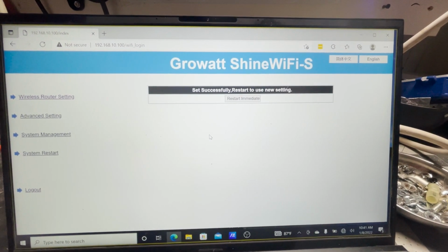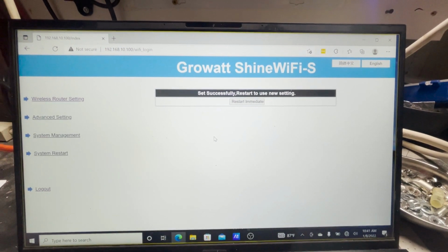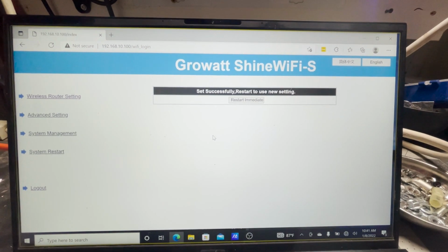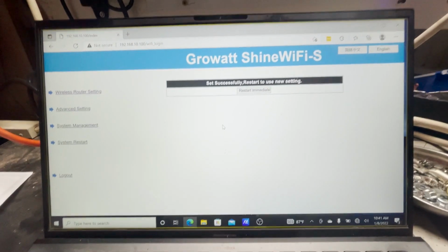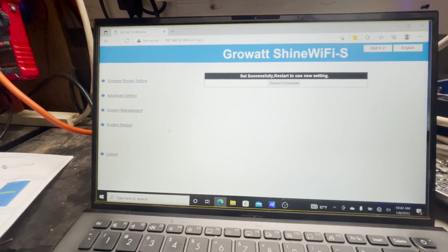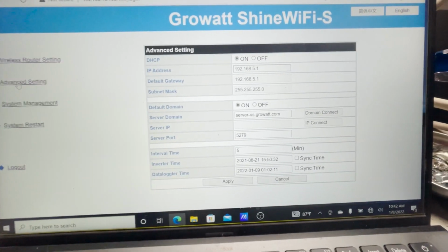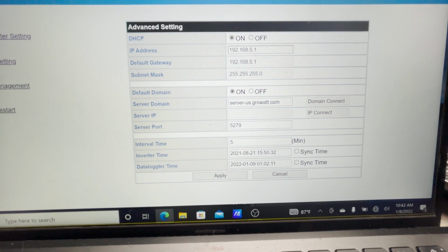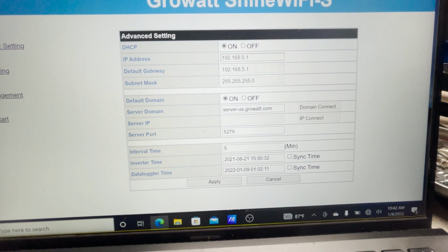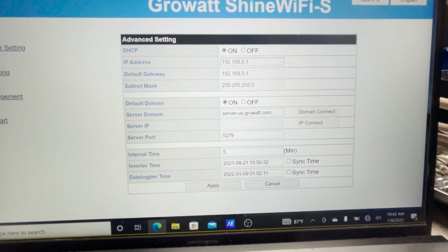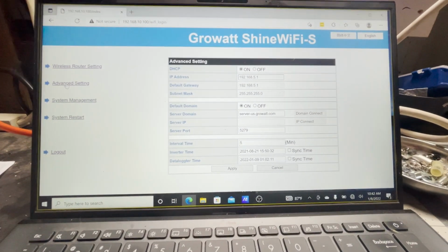But here's one thing that I want to point out. If you live in the US, when you go to the Growatt server online, it sends you to server-us.growatt.com. And you need to change that setting before you restart. So if you look down here on advanced settings, make sure that it says server-us.growatt.com. The first one I installed did not have that US in there, and it gave me some problems.